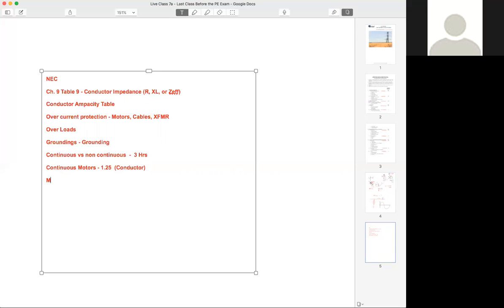What about if I've got multiple loads fed from the same conductor? Who gets multiplied by 1.25? The largest motor, awesome. And then we just add the sum of the rest, right?